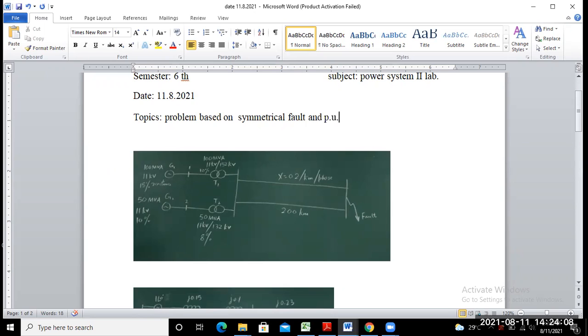One more thing we already discussed: if any reactance value is given at a specified MVA and base kilovolt rating, and you want to find the per unit reactance at another MVA base or kilovolt base, then per unit new equals per unit old into MVA rating new divided by MVA rating old, into kV base old whole square divided by kV base new whole square. Based on this formula, we will solve one power system problem related to symmetrical fault.